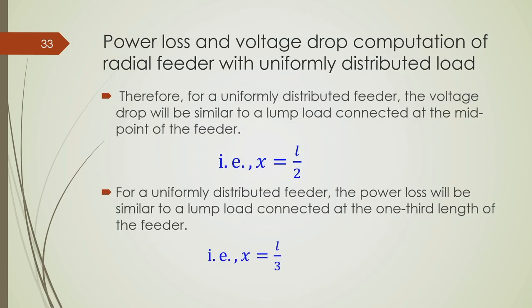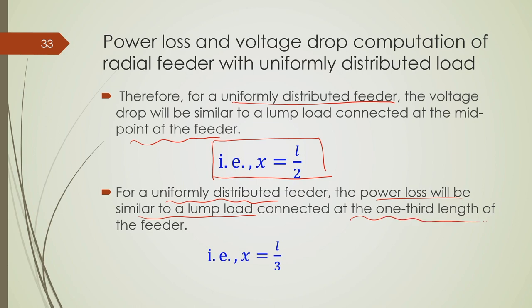Alternatively: for a uniformly distributed feeder, the voltage drop is equivalent to the lumped load connected at the midpoint of the feeder. For a uniformly distributed feeder, the power loss is equivalent to the lumped load connected at one-third of the feeder length. This is something new for this type of analysis.